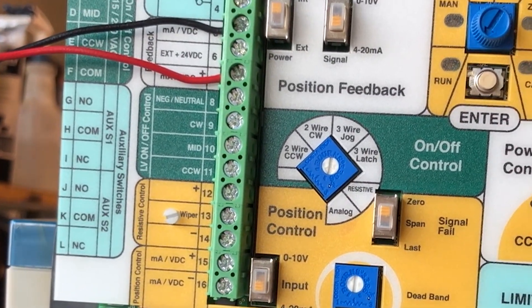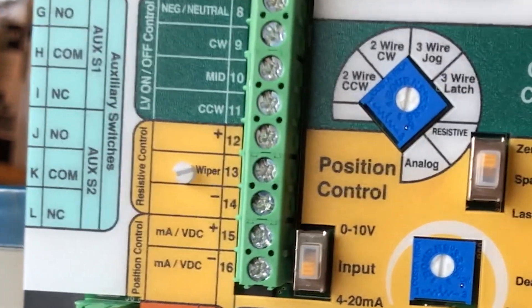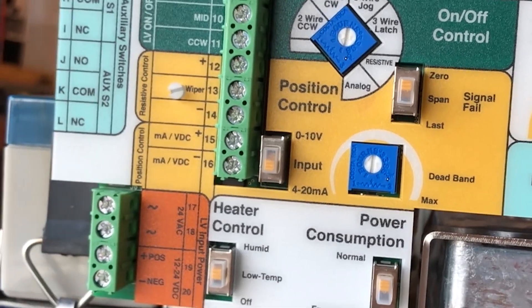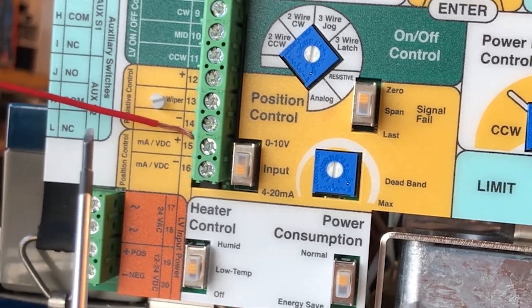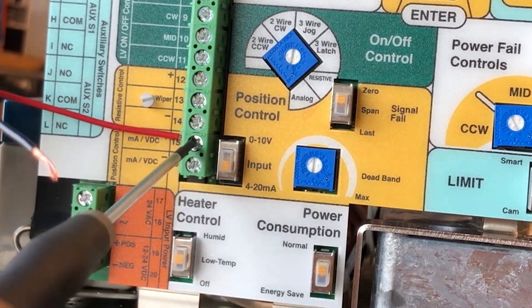Next we're going to wire in our milliamp signal for position control for the actuator and that's going to be terminals 15 and 16. 15 being positive, 16 being negative. This is our 4 to 20 milliamp signal.